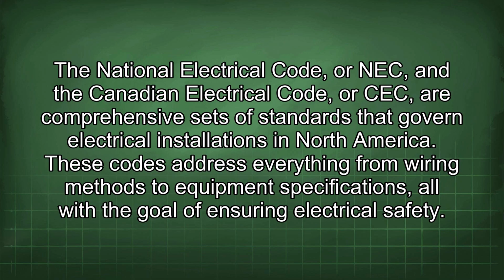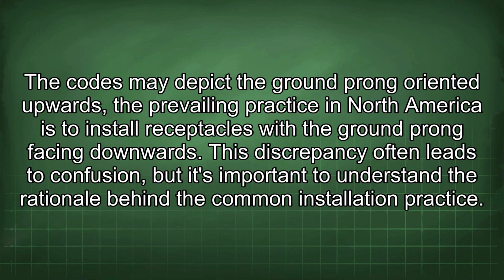The National Electrical Code, or NEC, and the Canadian Electrical Code, or CEC, are comprehensive sets of standards that govern electrical installations in North America. These codes address everything from wiring methods to equipment specifications, all with the goal of ensuring electrical safety. The codes may depict the ground prong oriented upwards. The prevailing practice in North America is to install receptacles with the ground prong facing downwards. This discrepancy often leads to confusion, but it's important to understand the rationale behind the common installation practice.